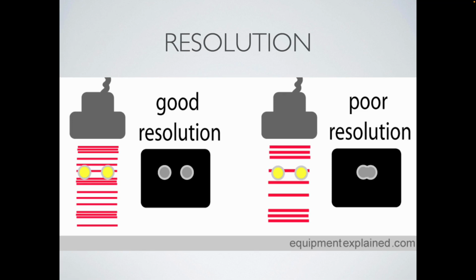Resolution obviously is going to be important. We talk about resolution when we talk about cameras, and it's the same principle that really applies to the ultrasound probes. It's the ability to discern two discrete items when they are present, or basically it's another term to talk about how crisp an item looks on ultrasound. It is dependent on the frequency of the probe. So in general, the higher the frequency of the probe, the better the resolution is. So the obvious question always is, why don't we just have all high frequency probes all the time for good resolution? Well, the problem, again, like we were talking about before, is that the high frequency probe beams become more attenuated at certain distances, so the depth that the high frequency probes can give is limited.